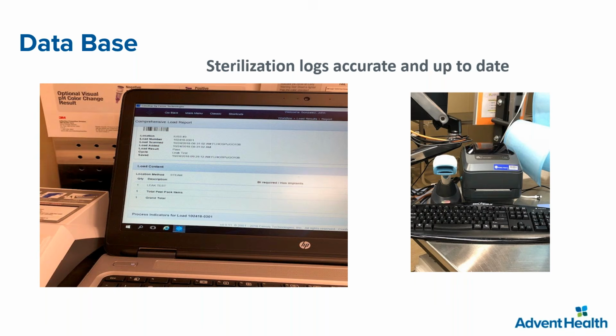Yes, if you want to do an audit, everything has to be precise. Everything has to be 1, 2, 3, 4. There's no working around. Oh no, they have binders. They keep the information in case they have a system malfunction. Yes, they keep that, and also they have an automatic process for following all the spore testing. Because if that spore came back positive, they have a way to recall any kind of item that was done in that load. Okay, and they follow what is called the perpetual calendar.